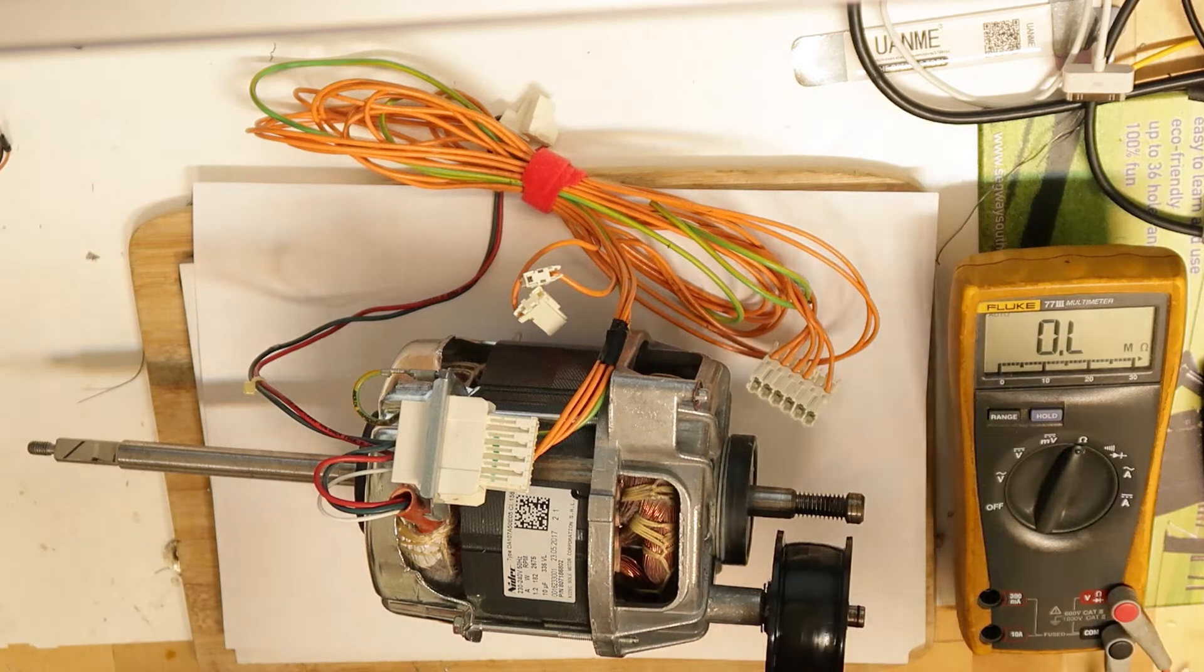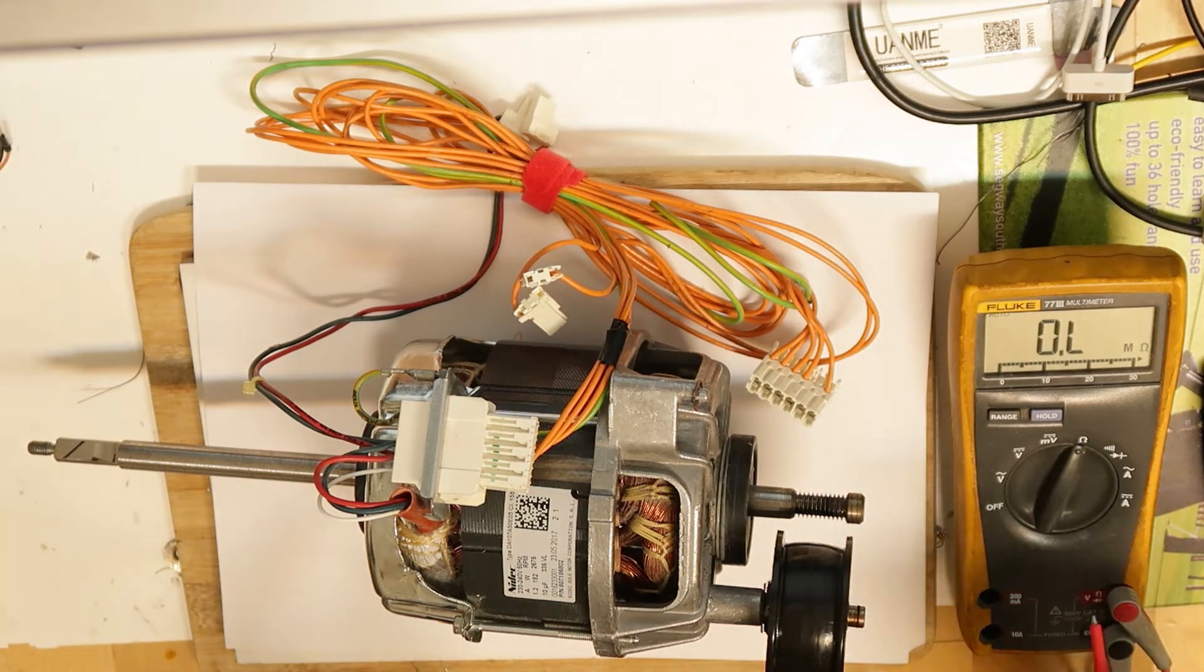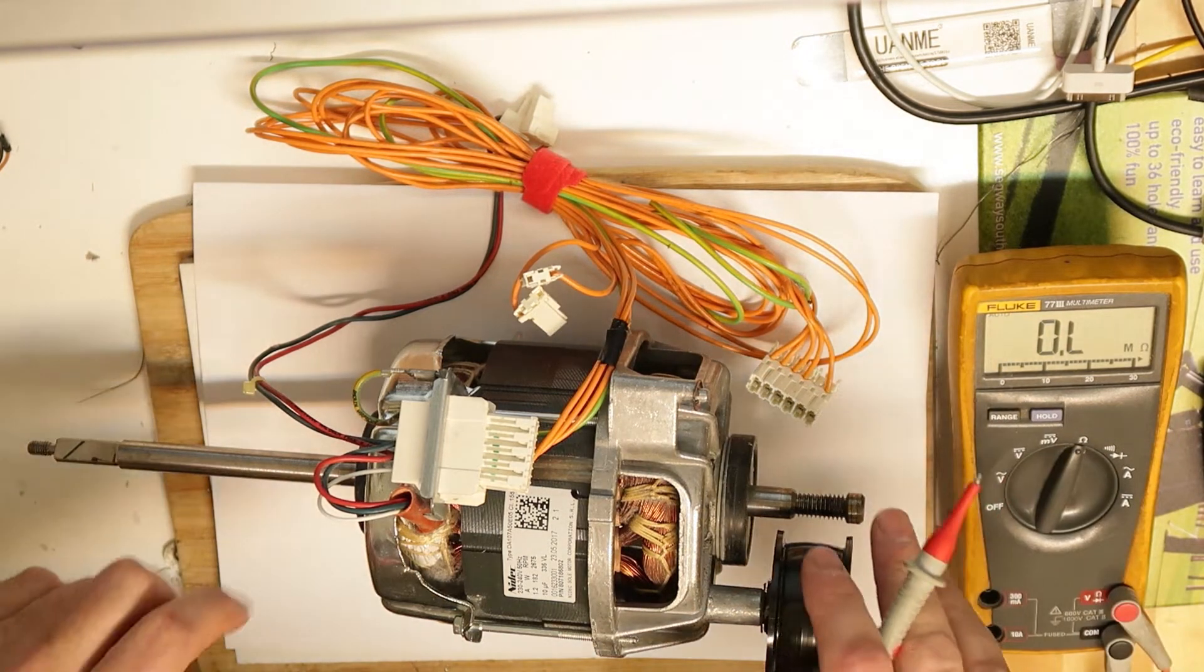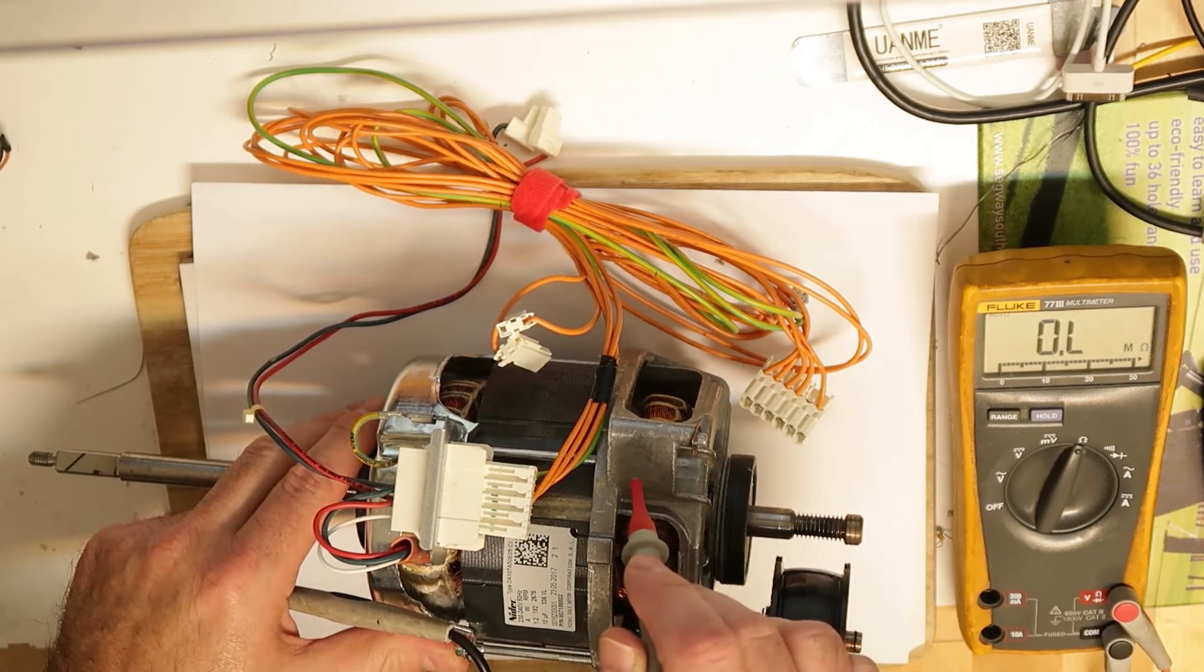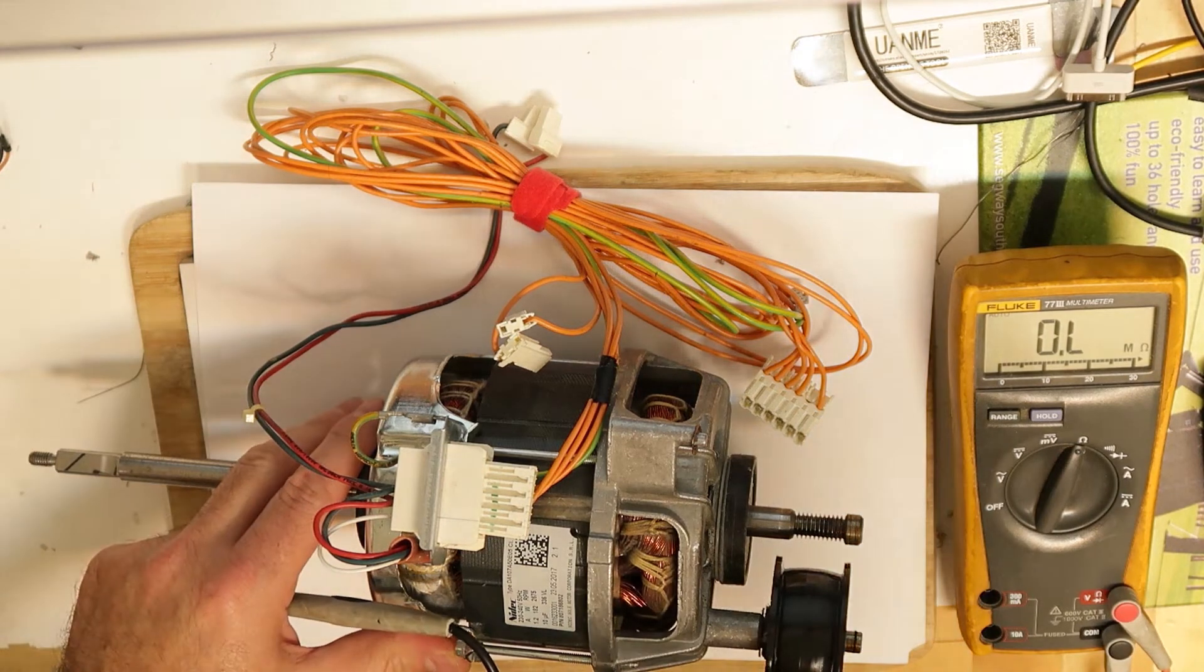Before doing anything, the first thing to measure - of course do not connect anything to the outlet, not yet - I want to check that I don't have a leakage from one of the wires of the motor to the chassis, because if you have that, you can die.